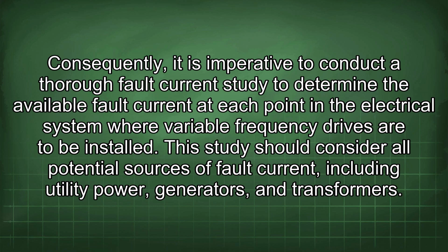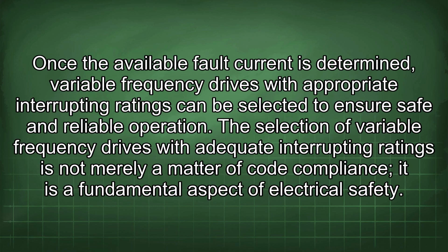This study should consider all potential sources of fault current, including utility power, generators, and transformers. Once the available fault current is determined, variable frequency drives with appropriate interrupting ratings can be selected to ensure safe and reliable operation. The selection of variable frequency drives with adequate interrupting ratings is not merely a matter of code compliance, it is a fundamental aspect of electrical safety.